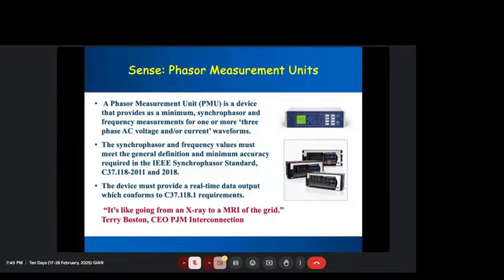A lot of different PMUs exist. Distribution PMUs exist also, with several different manufacturers. One of the manufacturers, which at least in the US is probably more common, is PSL, micro PMU. So synchrophasor and frequency values have to meet a certain standard, and the standard was C37.118, which came in 2011. It was revised in 2018, and then there were a lot more parts, like point one, which is about electrical parameters, and point two, which is about communication.